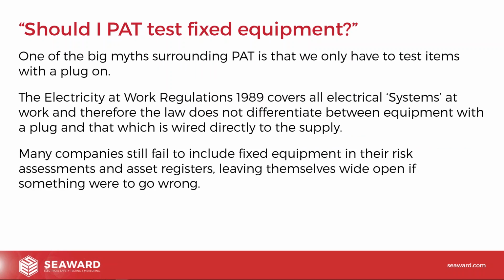So just going back to the topic of testing fixed equipment, and again, one of the big myths surrounding PAT testing is that we only test everything with a plug on. And as we've said, the Electricity at Work Regulations just cover systems. It doesn't say with a plug, without a plug. And generally, if it poses a risk to the user, then we should be doing something to make sure it's safe.